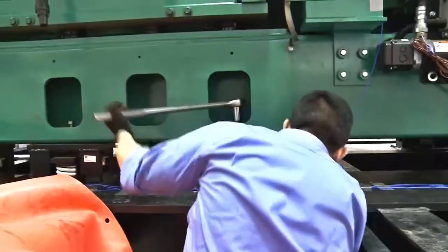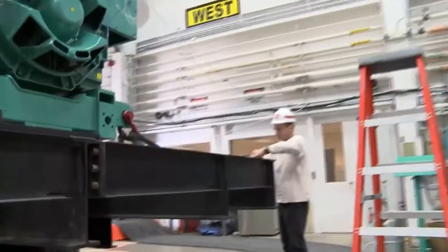Once the unit is in position and all the accelerometers are located in the proper position, the table will then be set in the triaxial mode and will be run for 30 seconds at its optimum level.